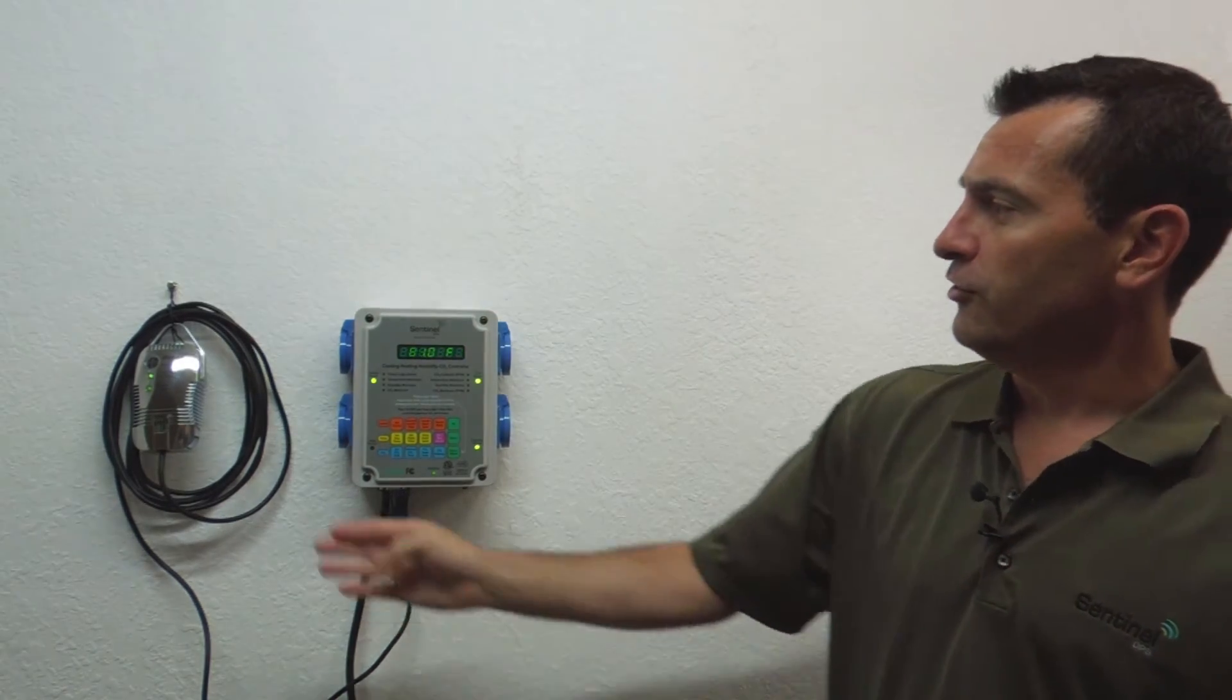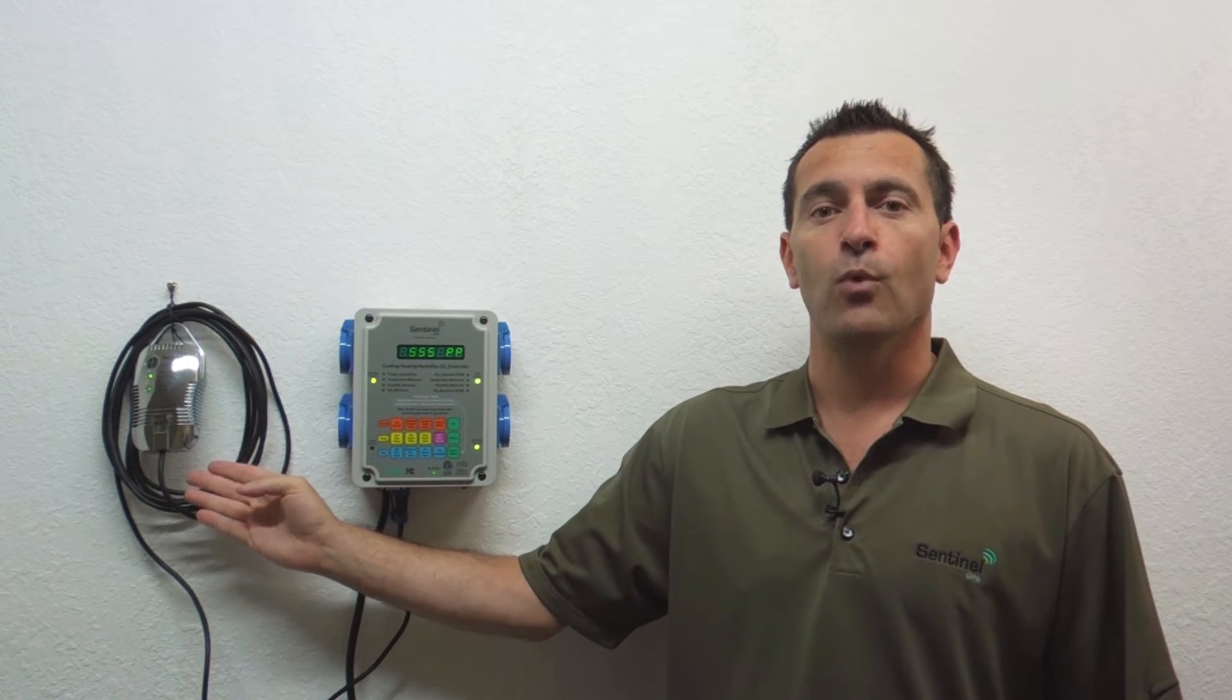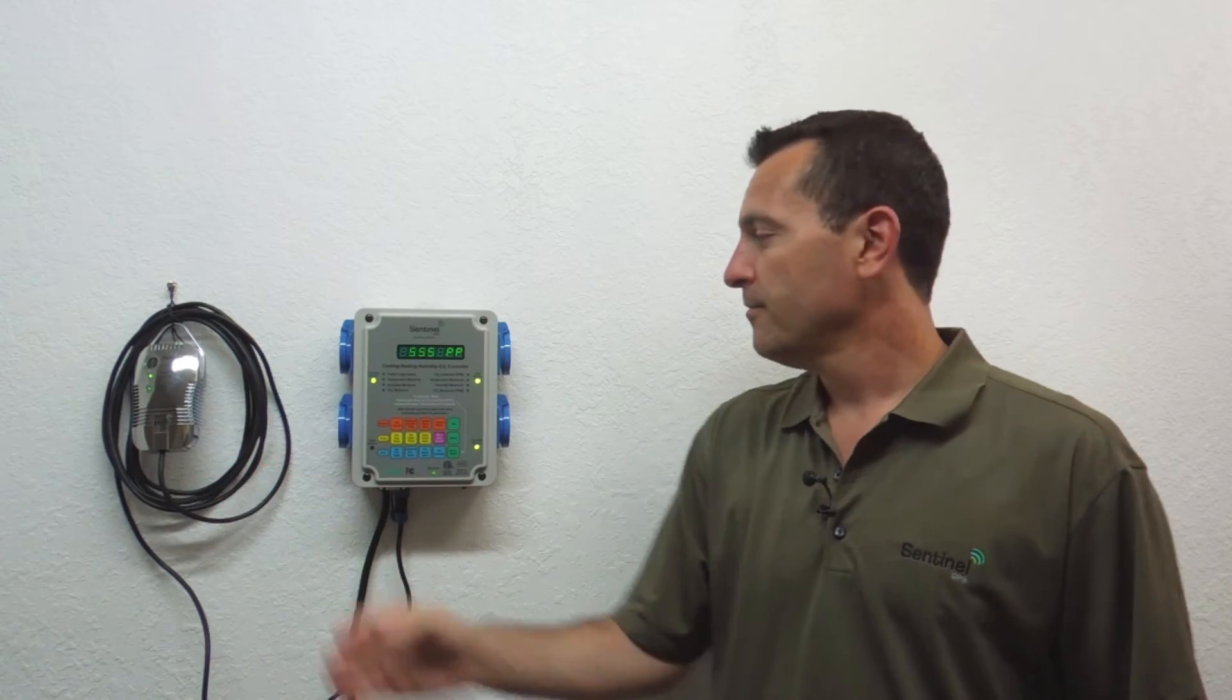The first thing to do is move the sensor to an outdoor fresh air location out of direct sunlight. Let the unit run and stabilize for one hour.